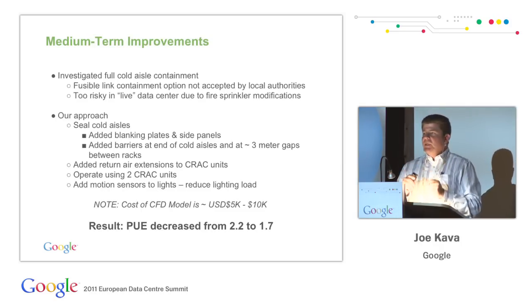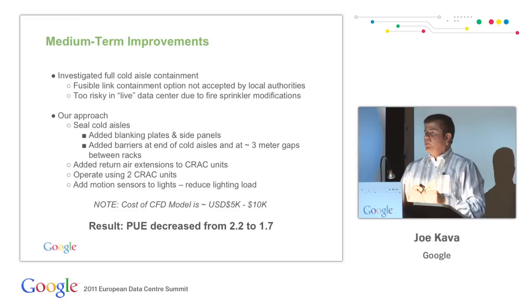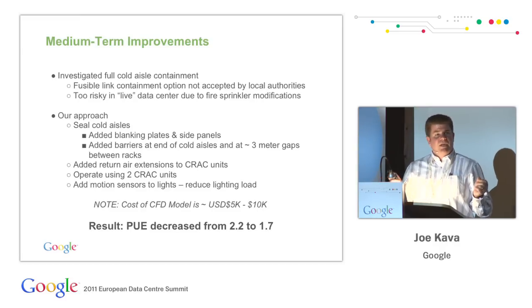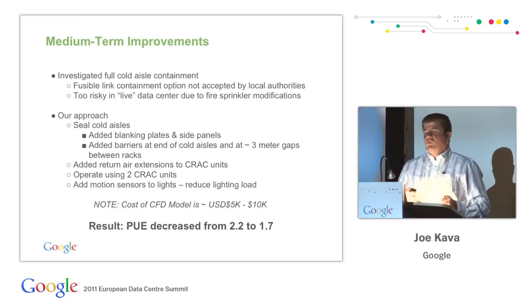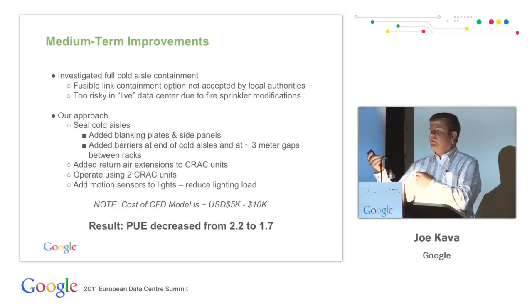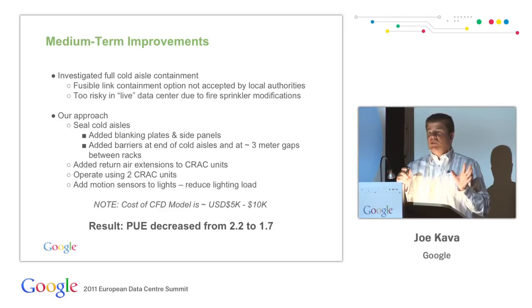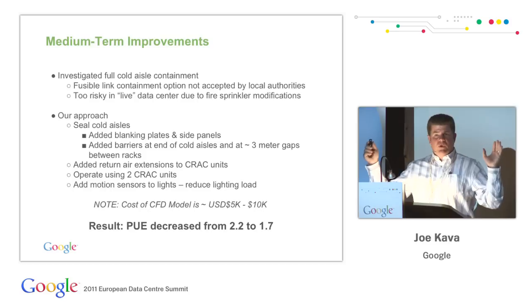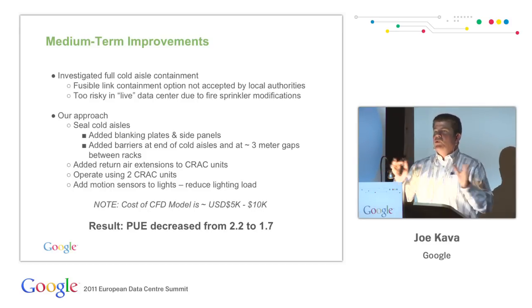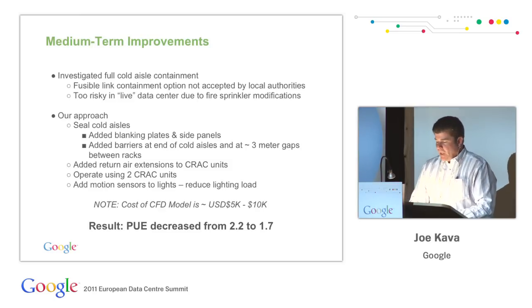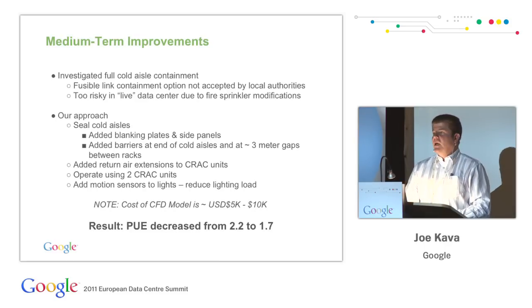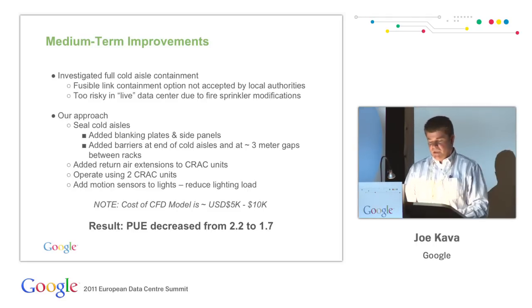Well, we were doing this work on a live data center, live server room. And we did not allow for any shutdown of any of the equipment. So in our opinion, working on an active sprinkler system above live IT equipment was probably a little bit too risky for what we wanted to do. So we decided to just focus on the best practices first without a full cold aisle containment. We can get a majority of the way with just the best practices of isolating and separating hot aisle from cold aisle. So simple things, blanking plates on the partially populated IT cabinets, end panels on the cabinets that were at the end of the row.